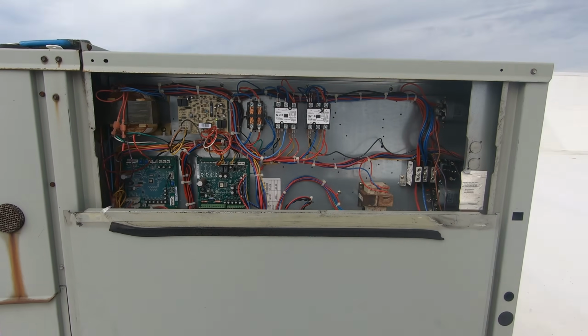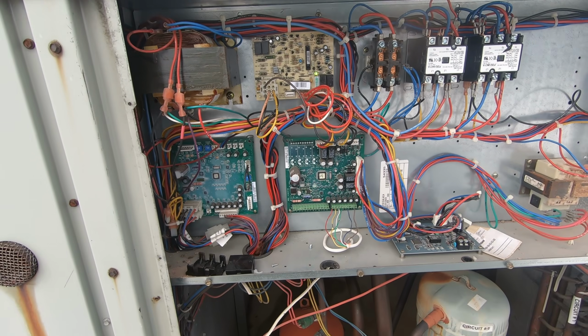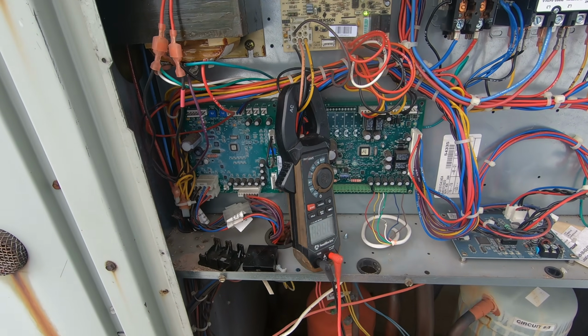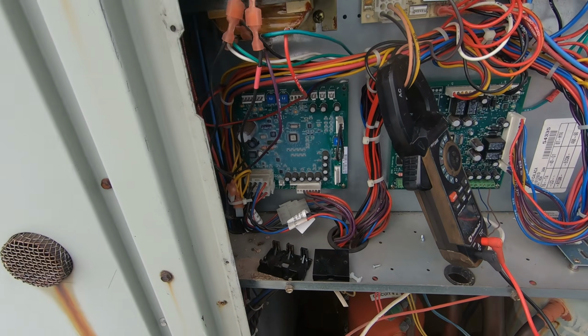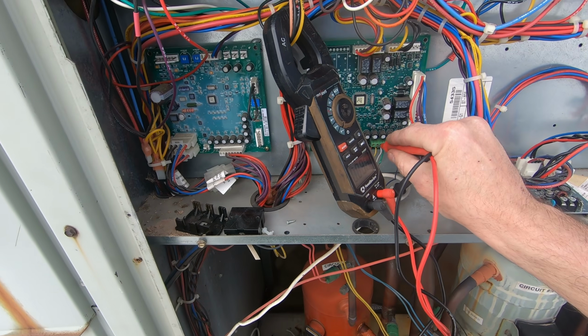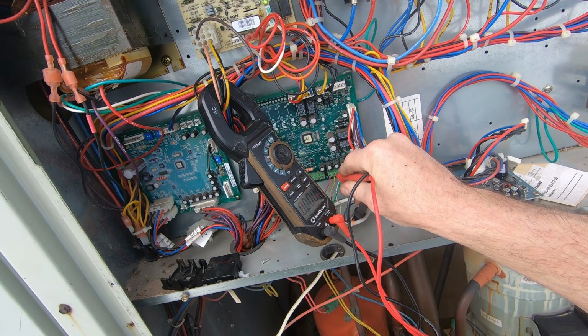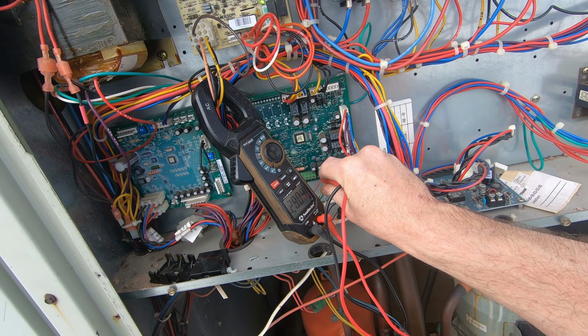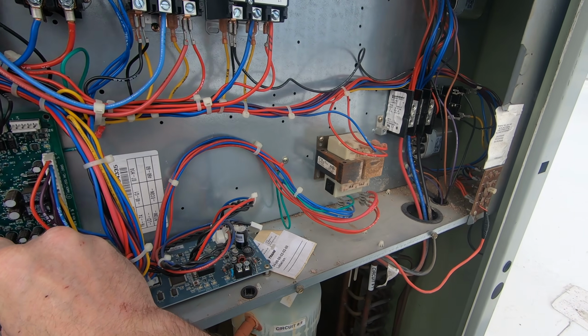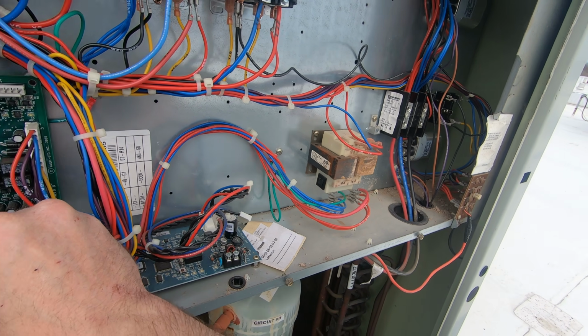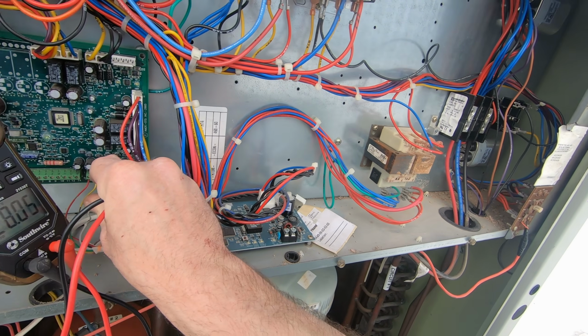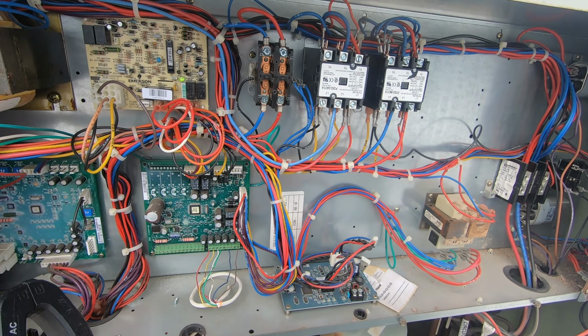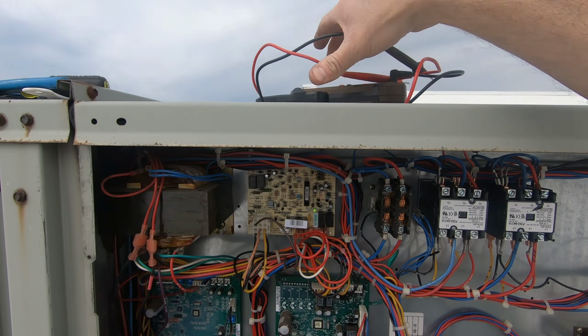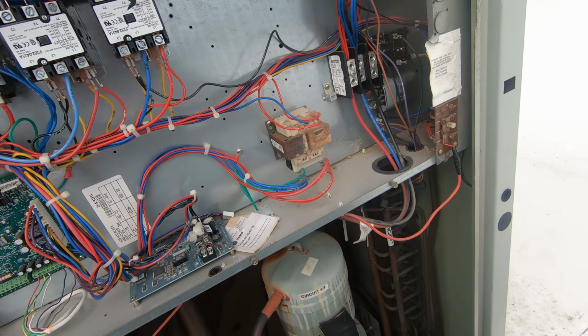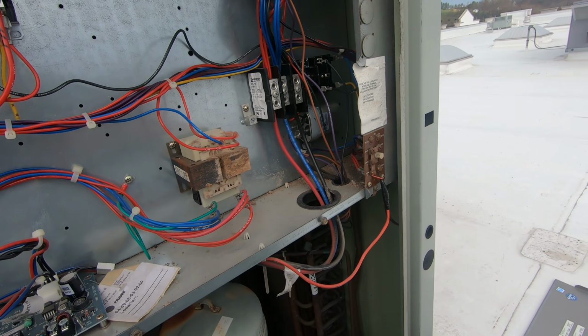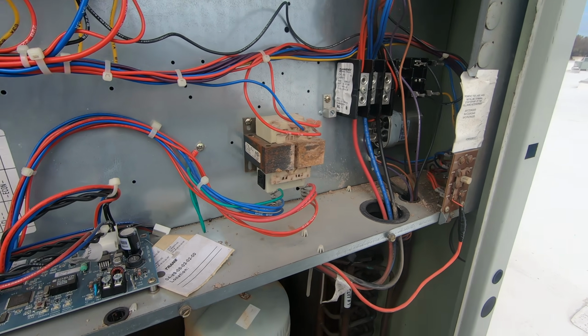Just was a second ago, but it's shut off. Yep, no call for Y. R, thermostat is not calling. The transformer is not tripped. And we do have a call for G. I'm happy with that. Not going to spend too much time here. It's clear what the problem was, and I got it taken care of.